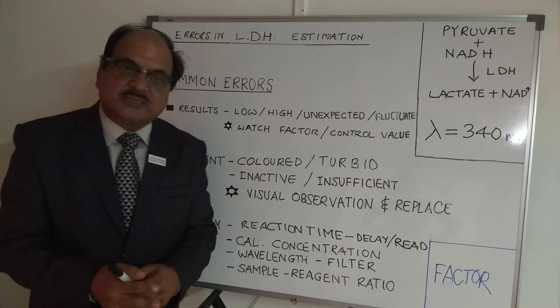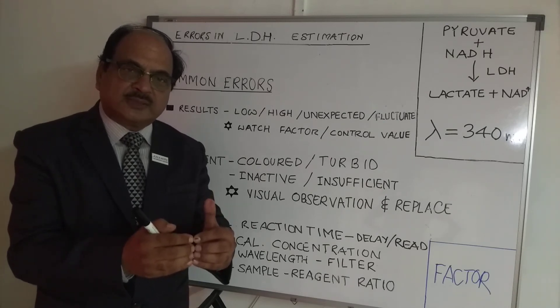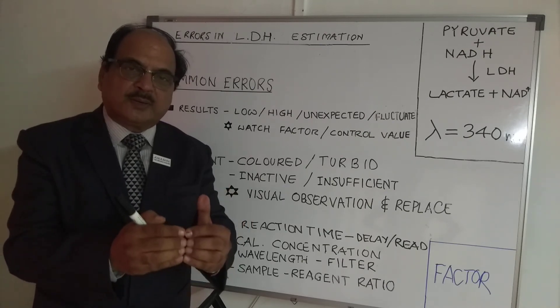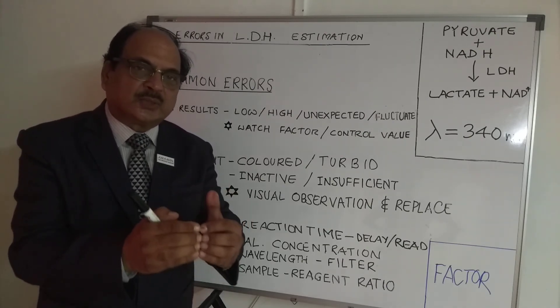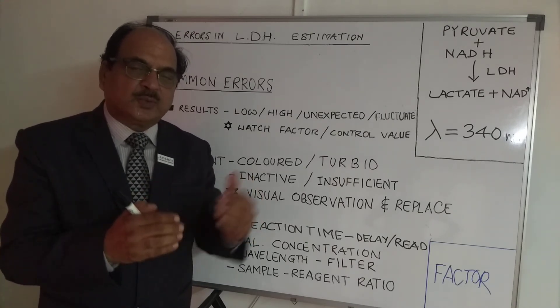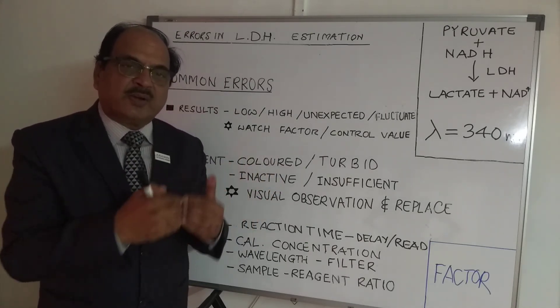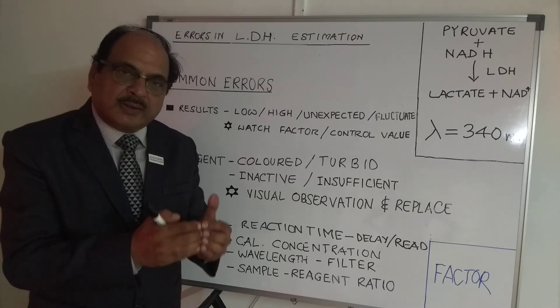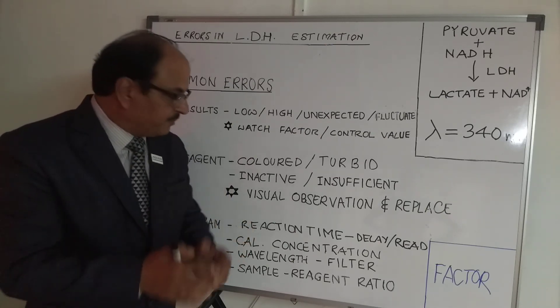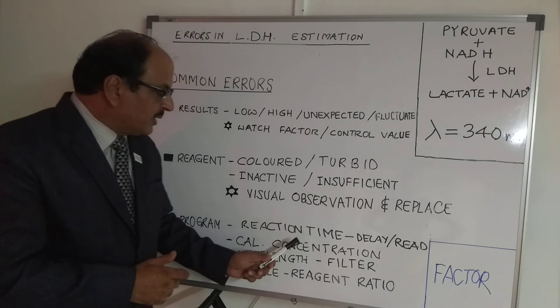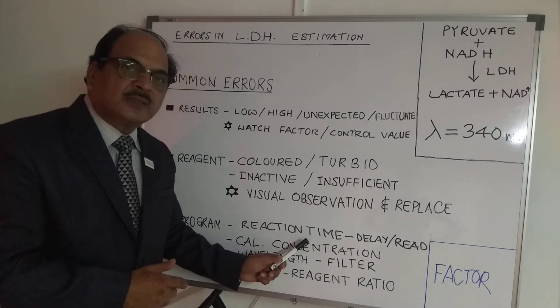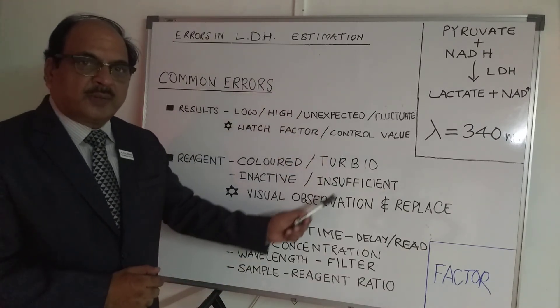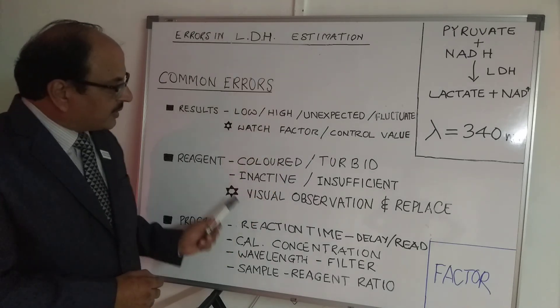Sample-to-reagent ratio is mentioned in the technical insert. For 1 mL reagent, the recommended sample volume is typically around 20 microliters. If needed, you may halve both volumes — 0.5 mL reagent and half the recommended sample volume — and results will still be acceptable. Importantly, whatever sample-to-reagent ratio is used for the calibrator must be the same for the sample.